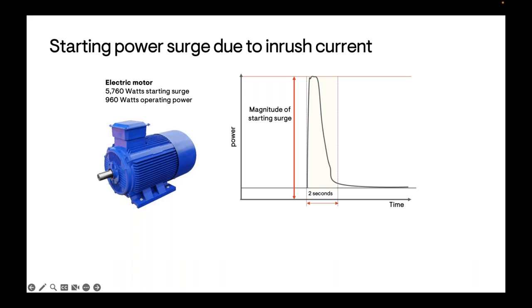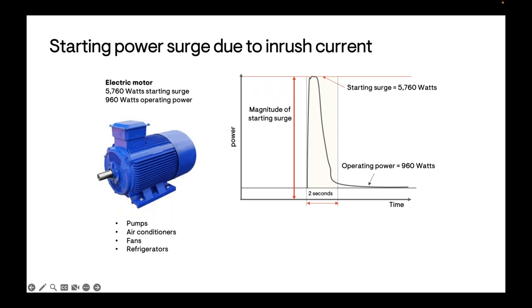A little more about power surge: this is primarily a concern with appliances that have a motor — air conditioners, refrigerators — which have a compressor motor inside. The most common types of motors have what's called inrush current for a couple of seconds when they first start up. In this example, the appliance demands about six times more power at startup than when running continuously — illustrated by a spike in power demand: about 6,000 watts for two seconds versus about 1,000 watts continuously. This is why it's very important to size the battery to handle the starting surge. Additional strategies like using soft starters can help.